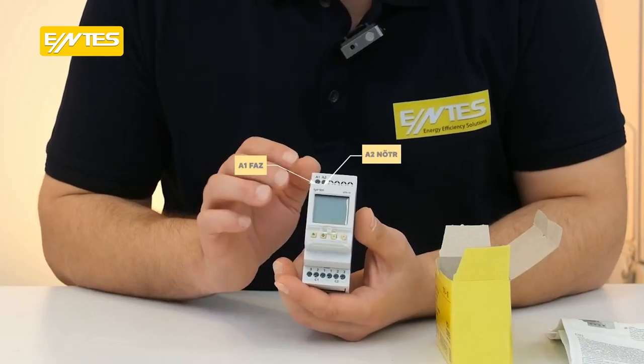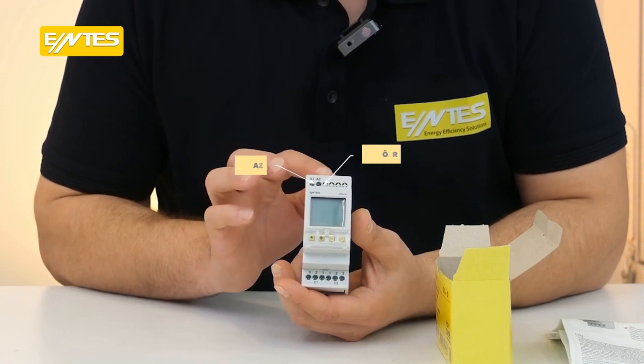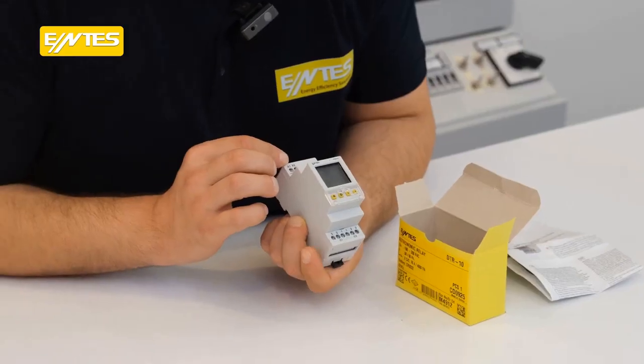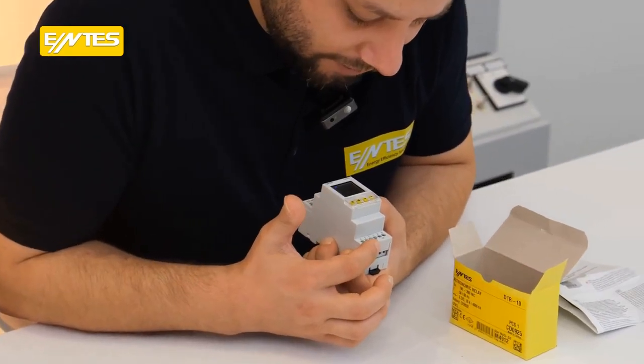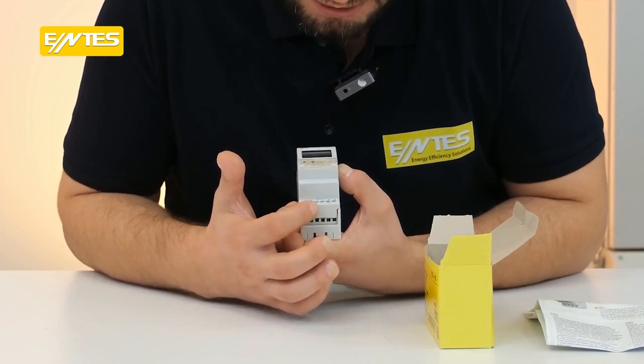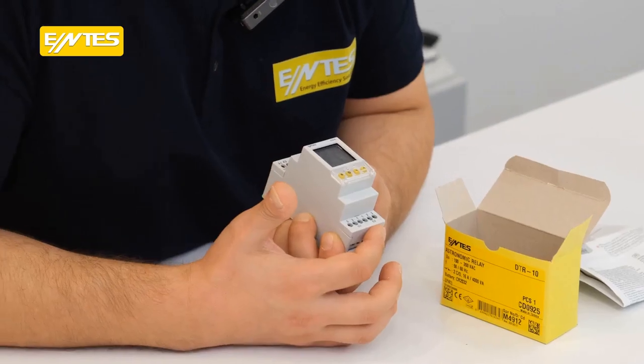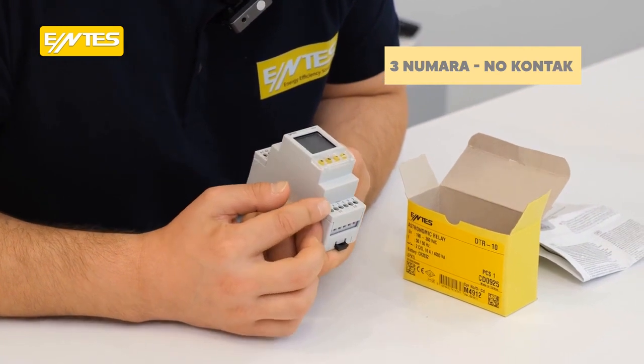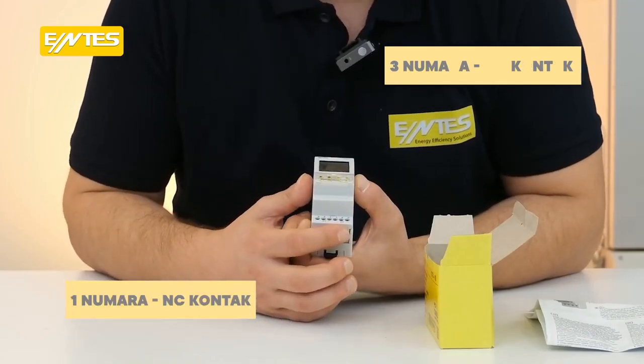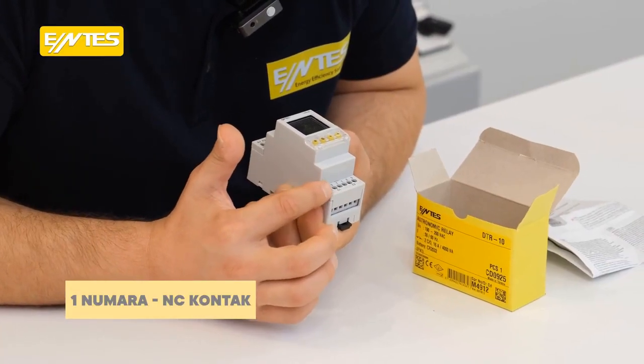The device is powered by A1 phase and A2 neutral. Since there are two relay outputs on the bottom side of A1, energy is supplied to the number 2 of C1 by jumping from A1. And if we are going to use the second relay, energy is supplied to the number 2 of C2. Number 3 is a NO contact in both relays. Number 1 is NC contact. We'll exit at number 3, we'll exit at NO.